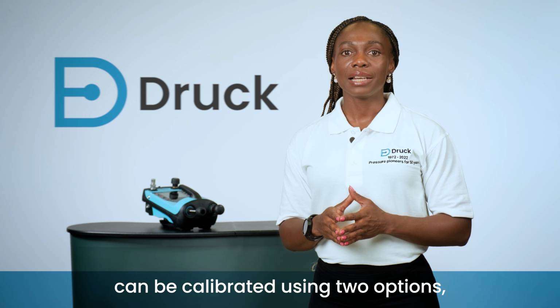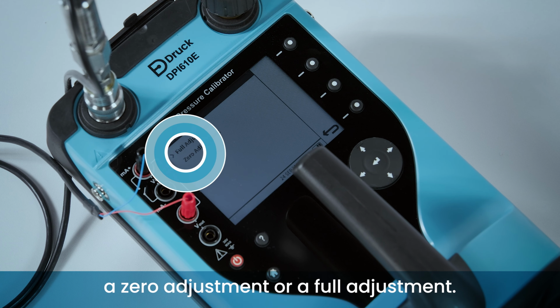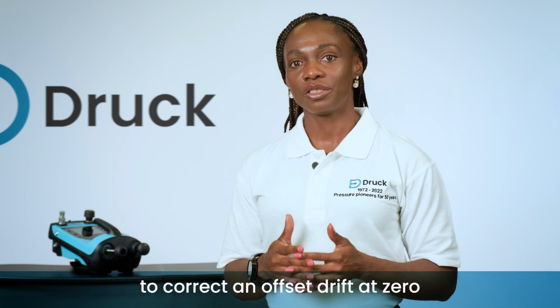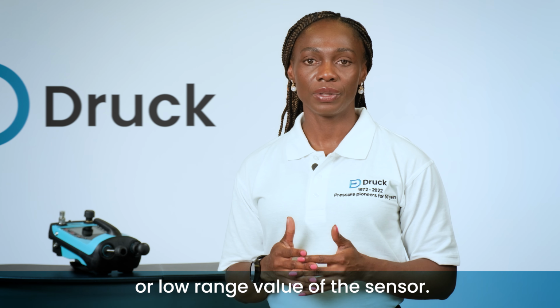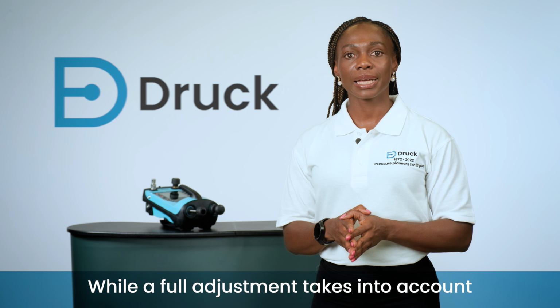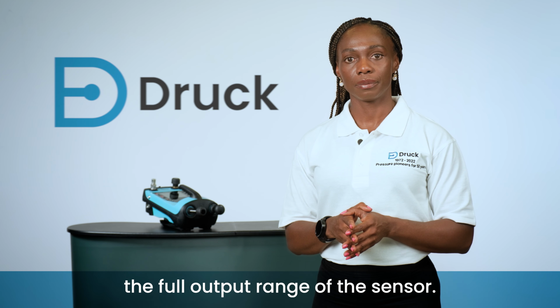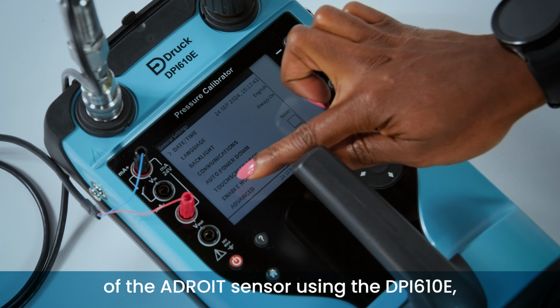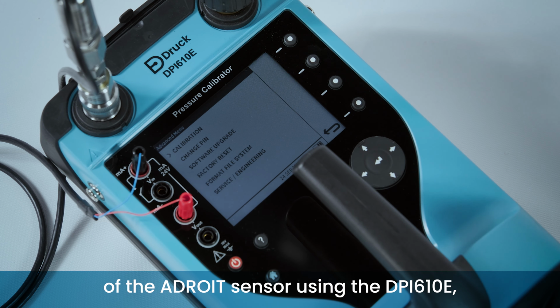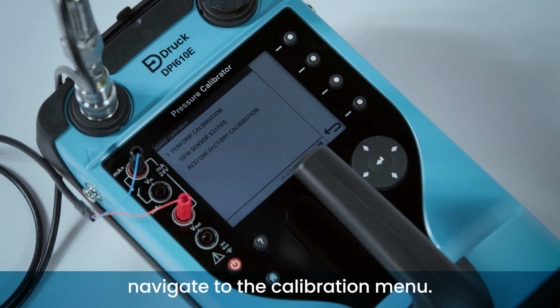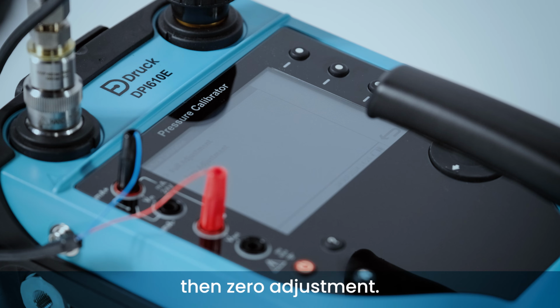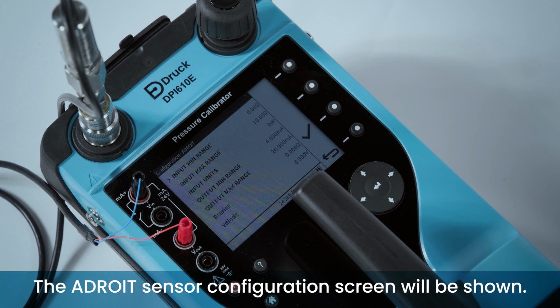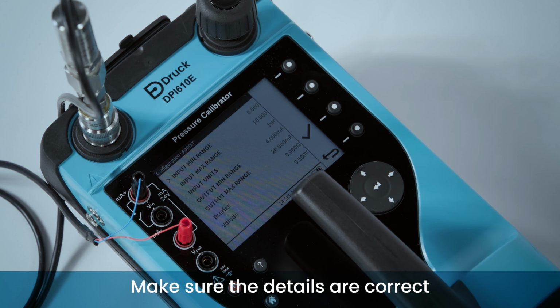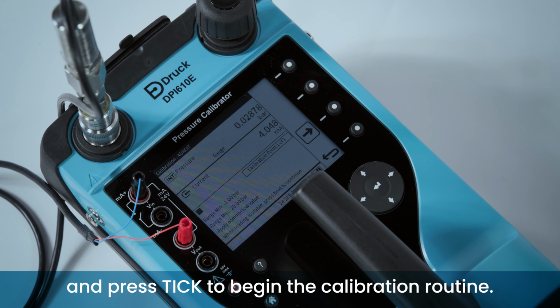The ADROIT sensor can be calibrated using two options, a zero adjustment or a full adjustment. A zero adjustment is done to correct an offset drift at zero or low range value of the sensor, while a full adjustment takes into account the full output range of the sensor. To perform a calibration adjustment of the ADROIT sensor using the DPI610E, navigate to the calibration menu. Select Perform Calibration and then Zero Adjustment. The ADROIT sensor configuration screen will be shown. Make sure the details are correct and press Tick to begin the calibration routine.